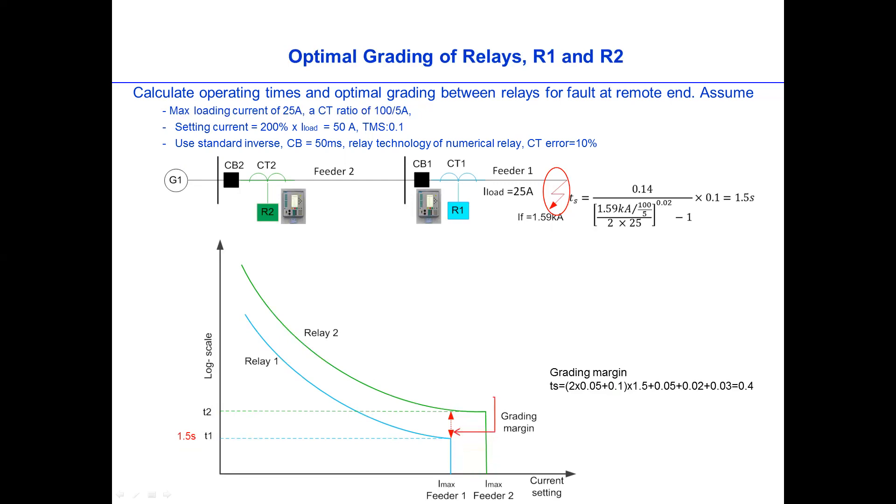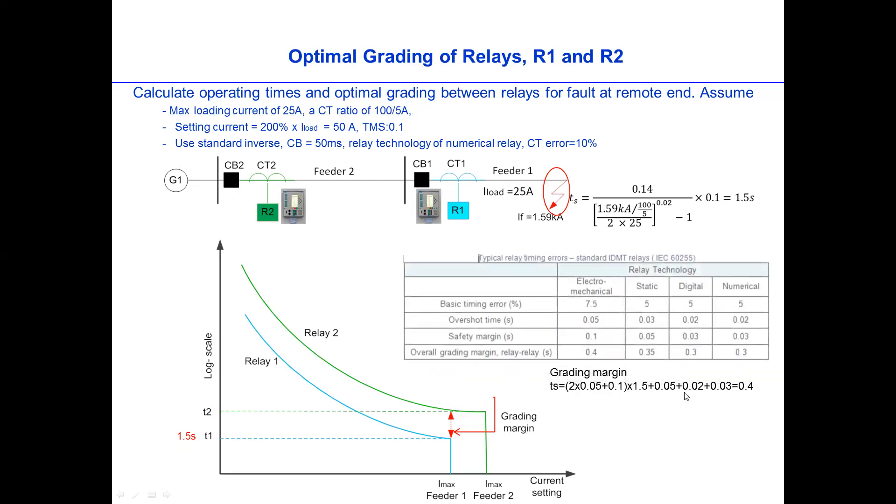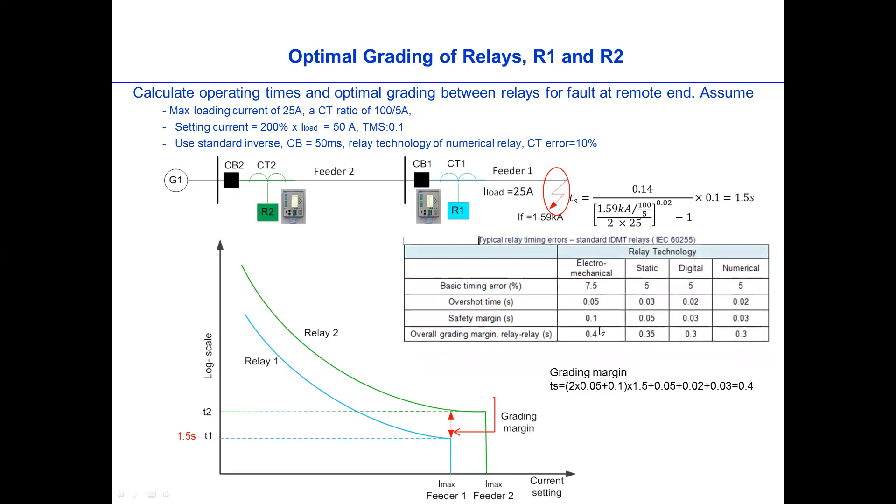And now we need to calculate the grading margin so that Relay 2 can provide the backup protection. Basically, if this Relay 1 fails, after how long will Relay 2 trip? That time, the delay time, we call it the grading margin. To find out the grading margin, we'll use this formula.